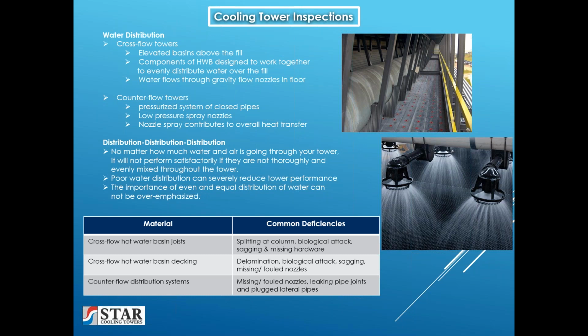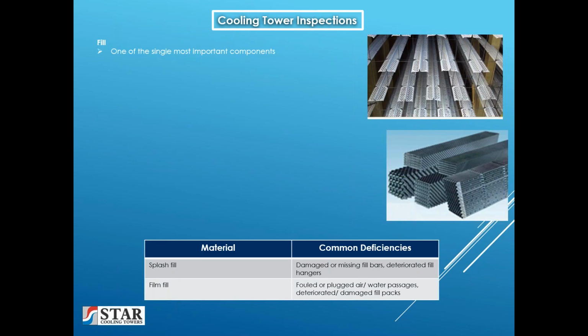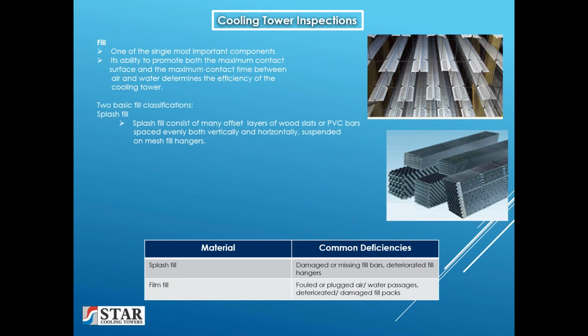Also, it's important to note that a missing nozzle creates a fire hose effect into your film fill and can create large holes all the way through the fill, which is going to allow air and water to bypass. The fill is one of the single most important components of a cooling tower. Its ability to promote both the maximum contact surface and the maximum contact time between air and water determines the efficiency of the cooling tower.